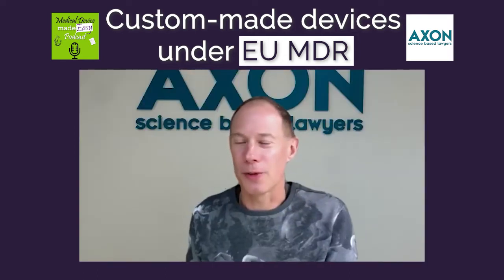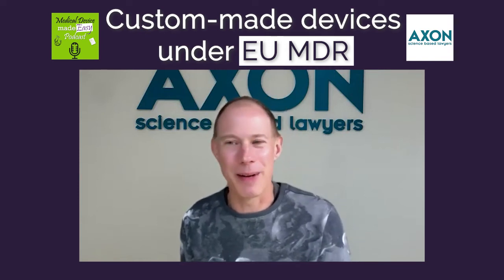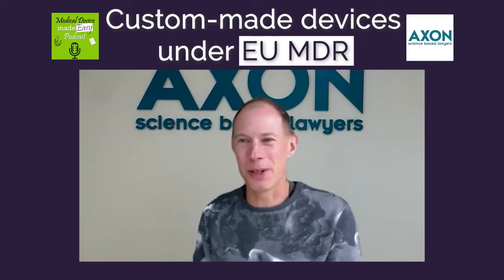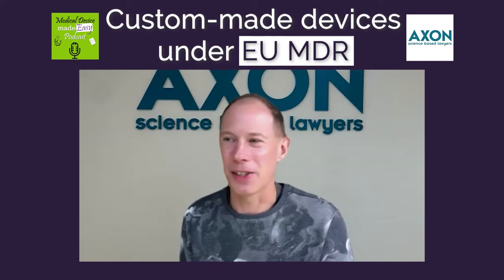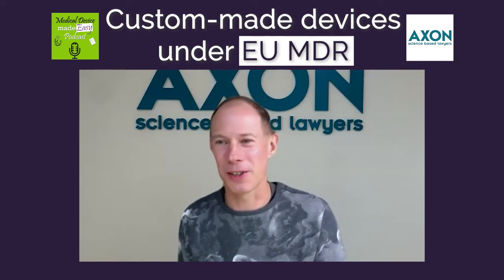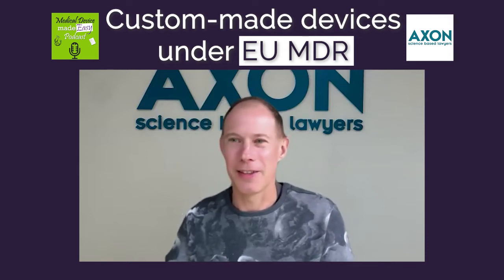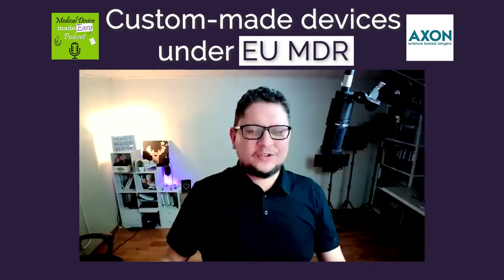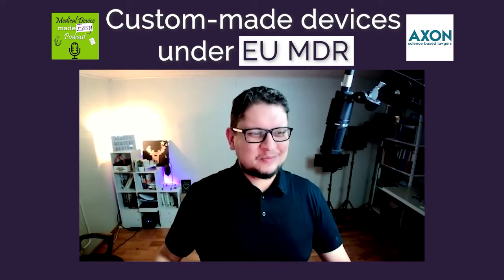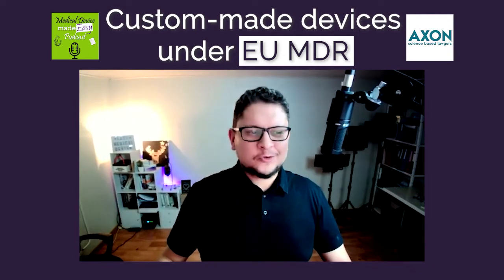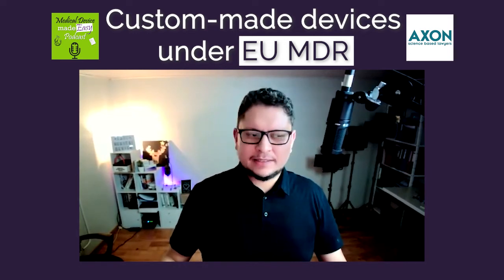And typically they ask for it if you have some very unhappy patients, which can happen with class 3 implants, for example. If you get your production process wrong, like, for example, you get standard post-operative infections for custom-made heart valves or something like that. So that wouldn't be nice. Yeah. So as we say, when everybody is happy, there is no issue. But when somebody is unhappy, then the problems start. And normally we have also one person, the same as a normal manufacturer. We have to have also a PRRC within our organization.